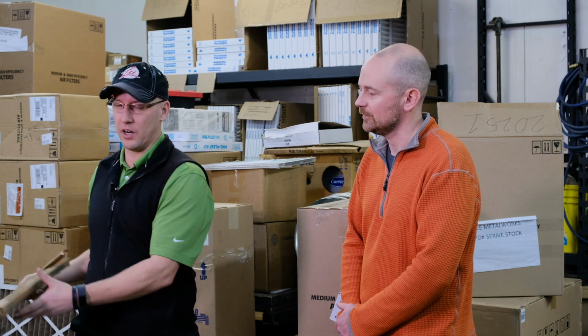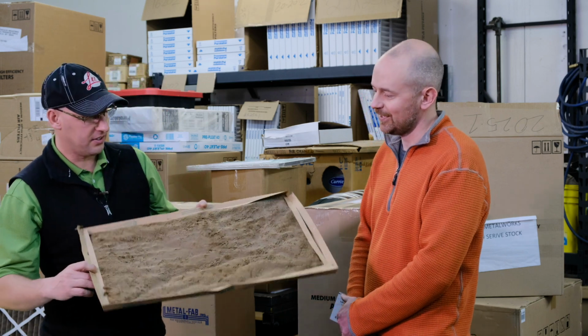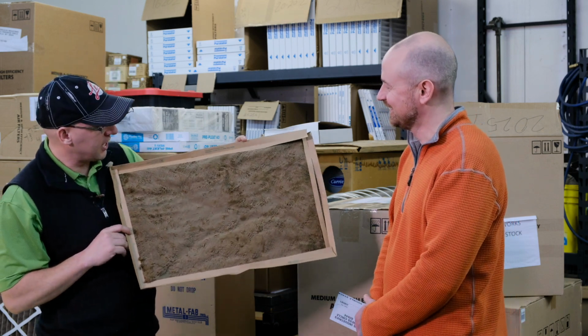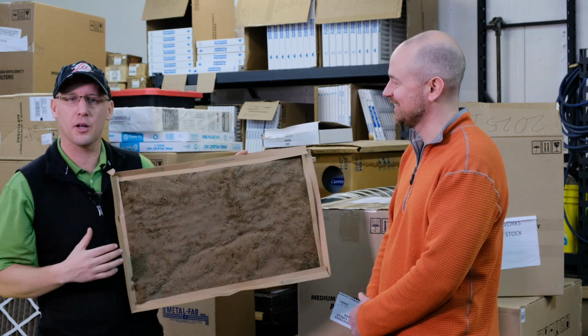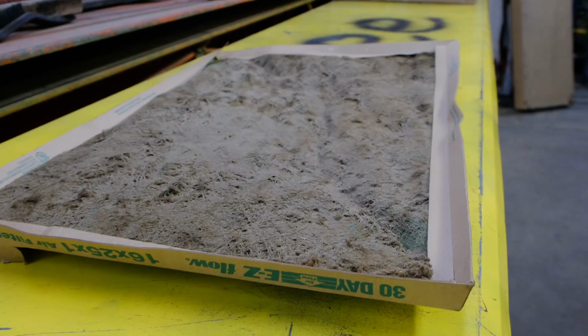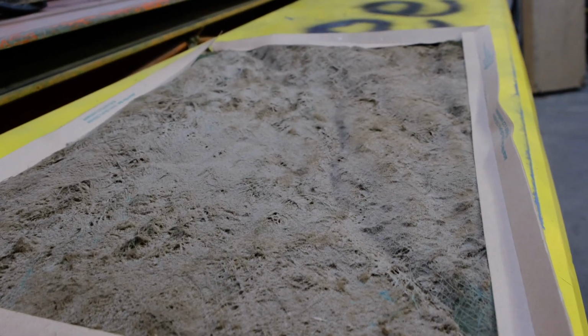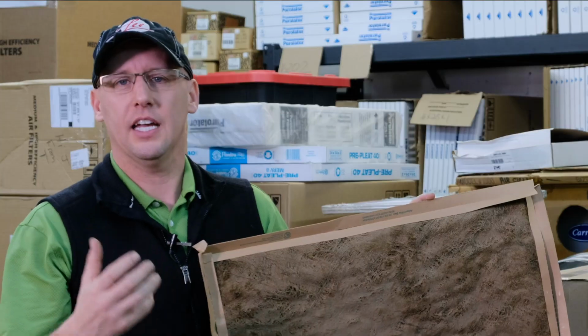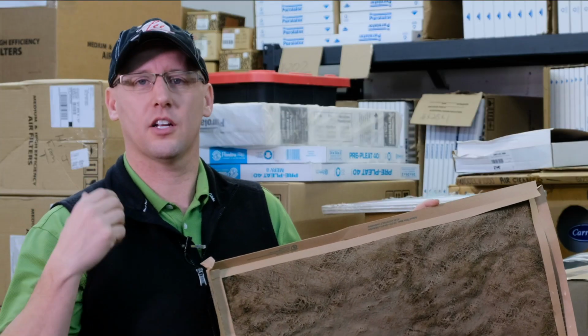Absolutely. And I have a couple of examples here to answer your question, because you're spot on, Nathan. The first one I have is a filter that's dirty. This is in bad shape. This is extremely dirty. It would make a great canvas, I guess, if you want to draw a picture on it. Here's an example of a filter that came out of a furnace that was being choked. When it's being choked, as we say in the industry, it's going to cause it to stress. It's going to work hard.